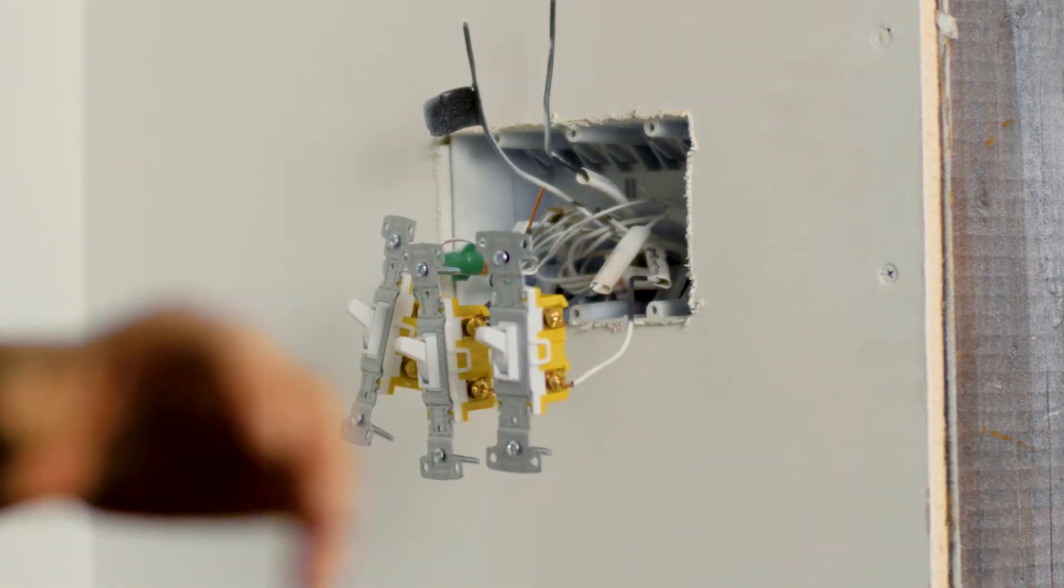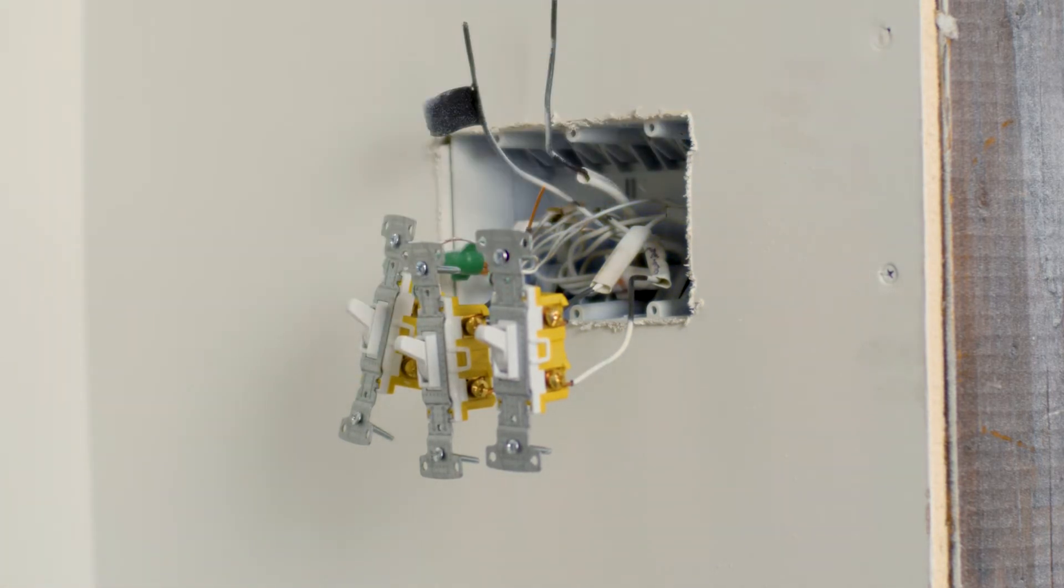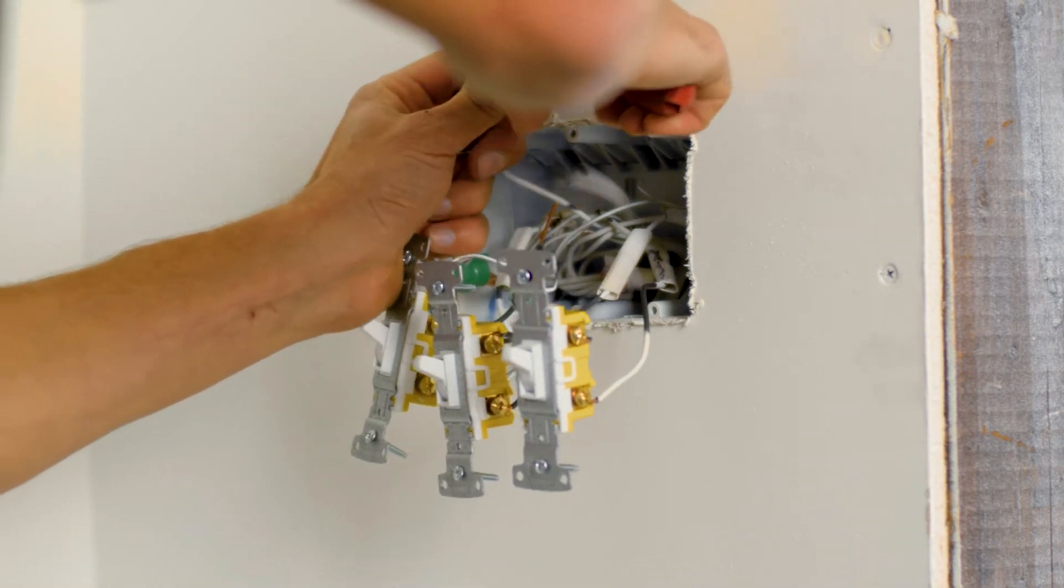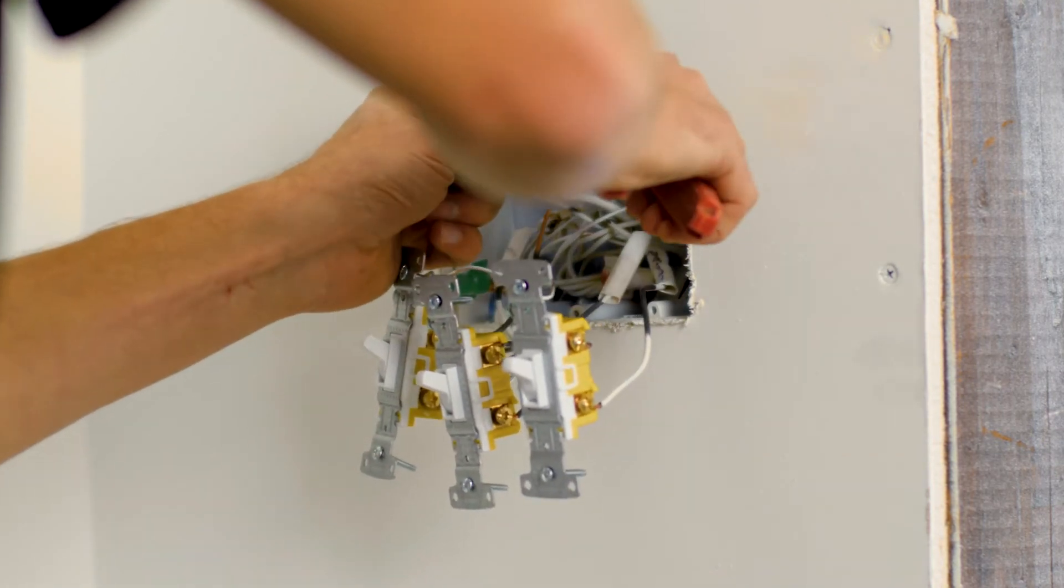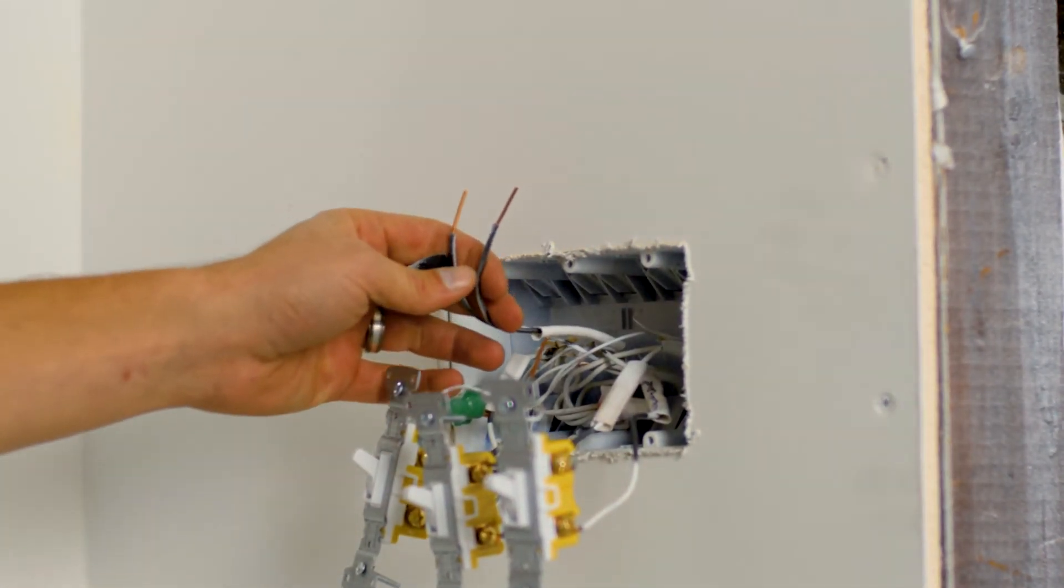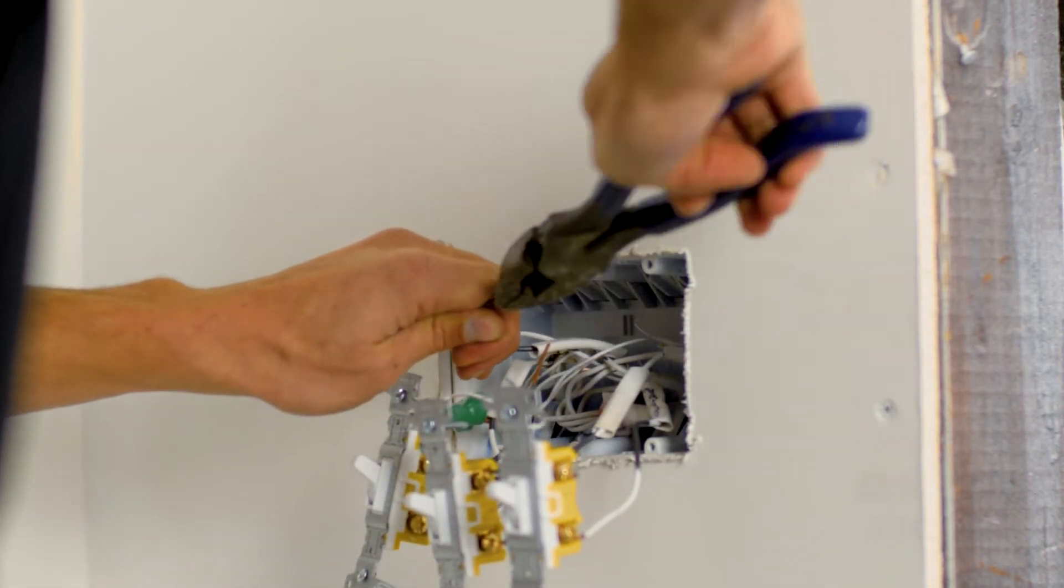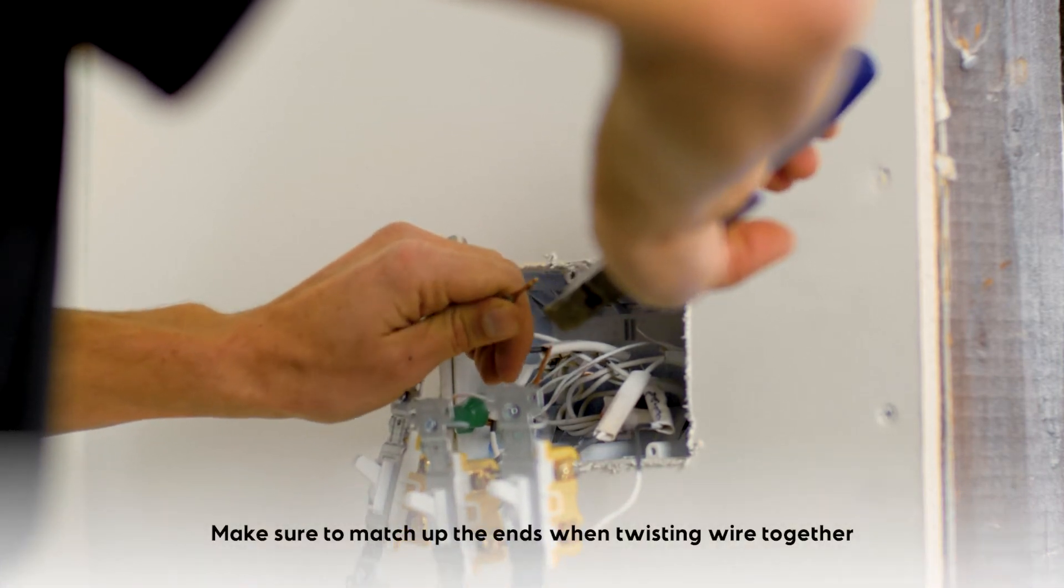Now, these are my hot conductors. I'm going to verify with my voltage detector, an insulated voltage detector. I'm going to verify that they're dead. I'm going to strip back just a little bit more, that's about an inch of conductor. I'm going to take my linesman pliers, the flats of my linesman pliers. I'm going to take two of my three conductors and give them a pre-twist. Careful to match up the ends.